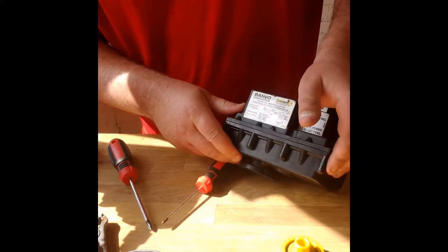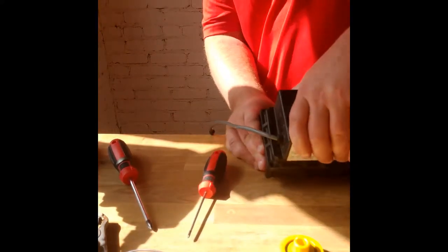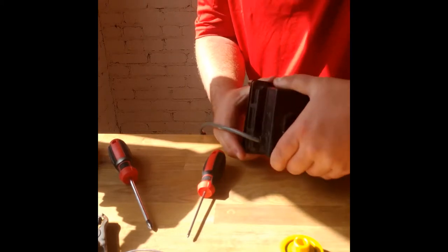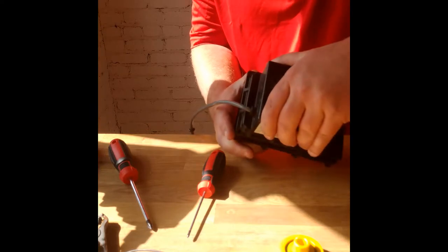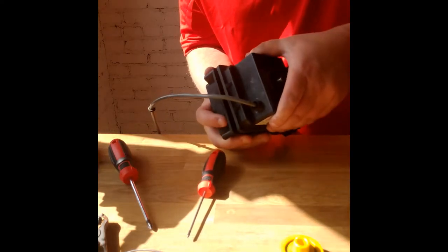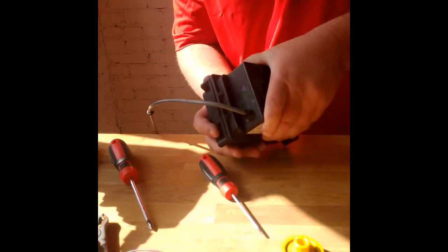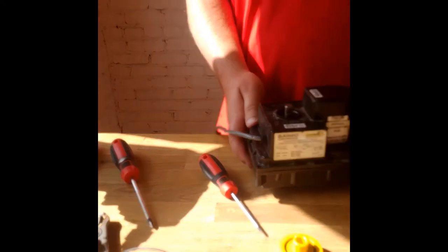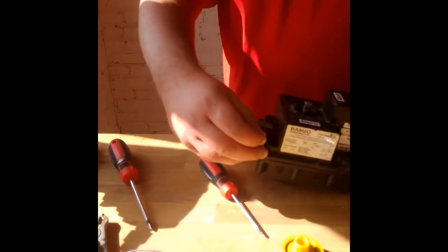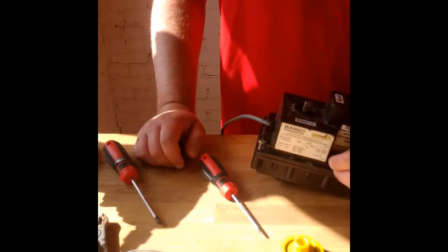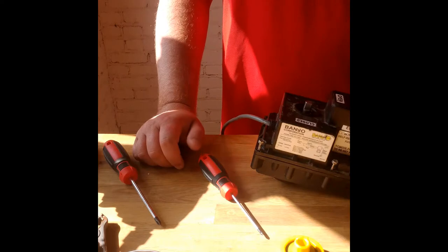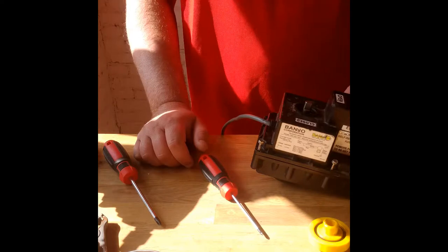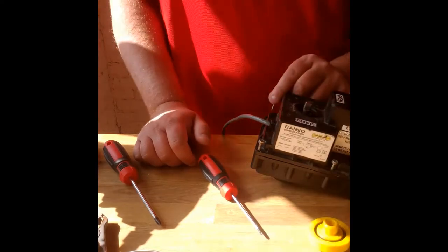And basically even if you don't have a banjo valve, if you just have a valve that has a motor in it, you know it doesn't have that instant on off, it takes a second, couple seconds to move, it's the same procedure. You disassemble, you take the assembly apart, you look for that relay. They all have it. They all have position sensors, switches just like that and those are the two things that mainly fail. Even after five, ten years of use, I've only seen a motor fail when the seals have failed and there's been corrosion in there.